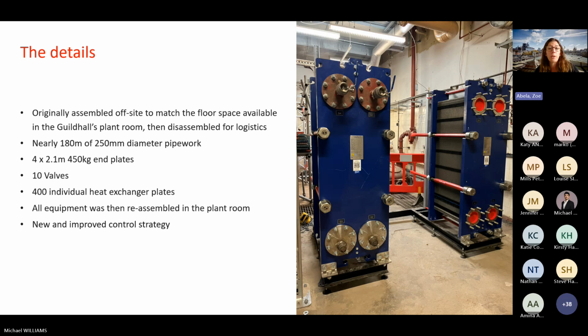This was to make them more manageable and also so they could fit through the door. Each section of pipe was flanged at the ends so they could be bolted together, reducing the need for hot works in the plant room. There were 4 end plates, each weighing 450 kilograms, and all the valves went down the ladder individually as in the previous video. The heat exchanger then had to be reassembled in the plant room just like a huge Meccano set.